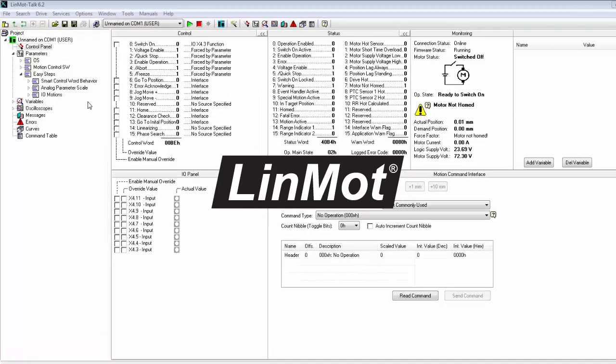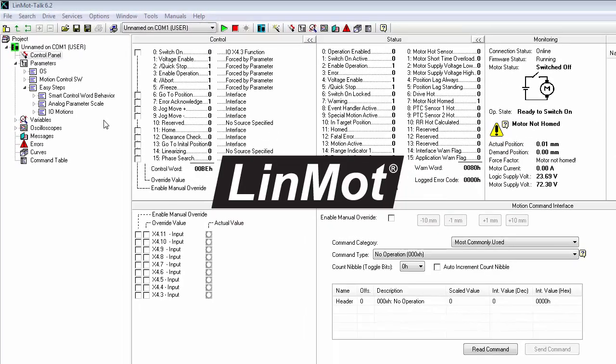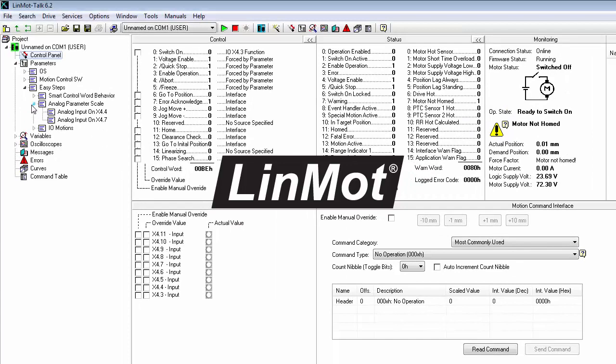Here's how you would do it. In this particular drive, you would connect your analog signal from the potentiometer to pin 4 of the X4 connector. So that's analog input on X4.4.